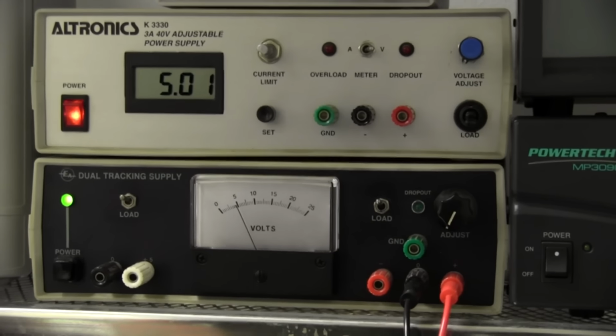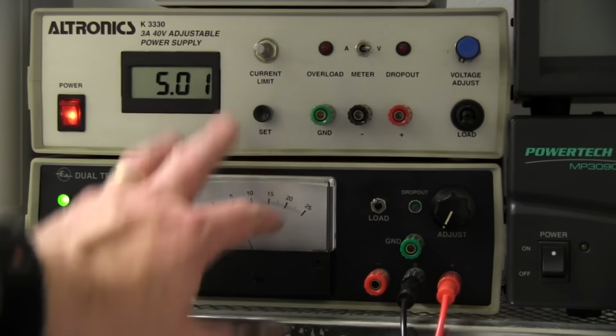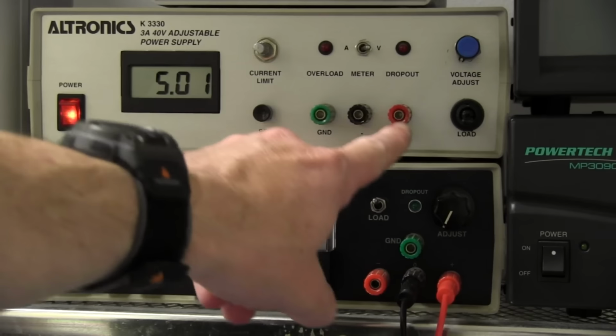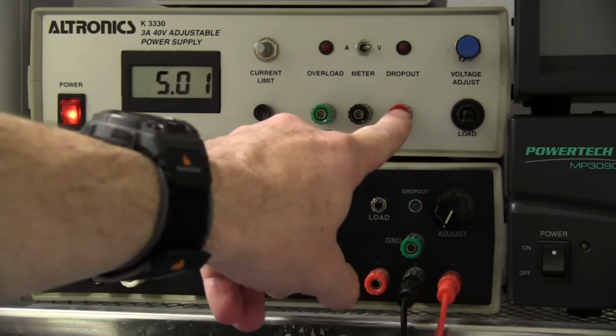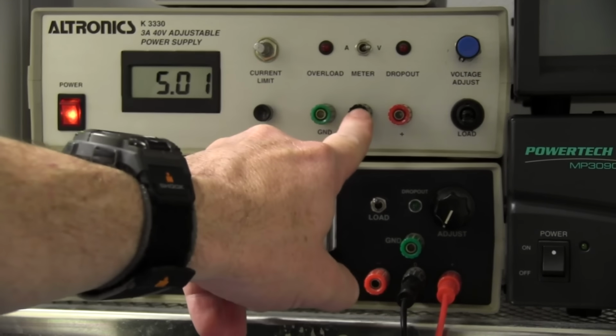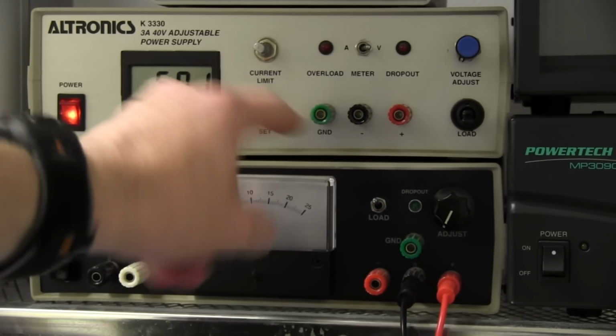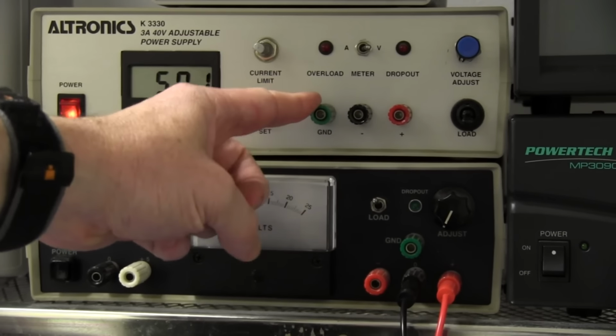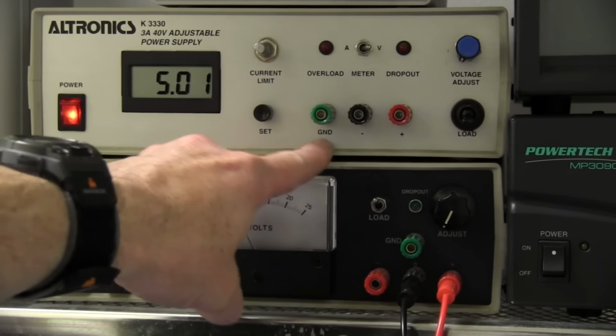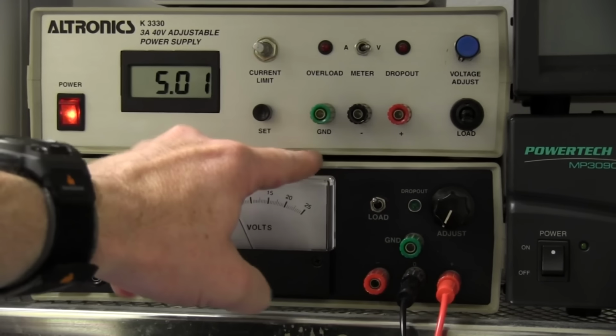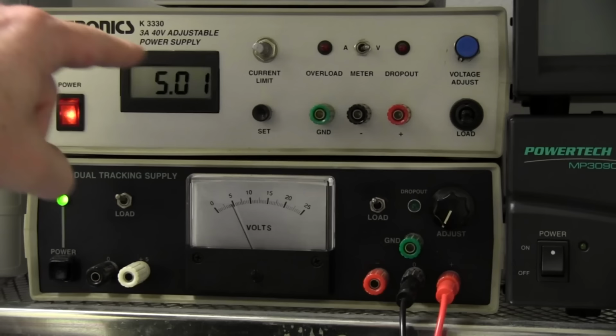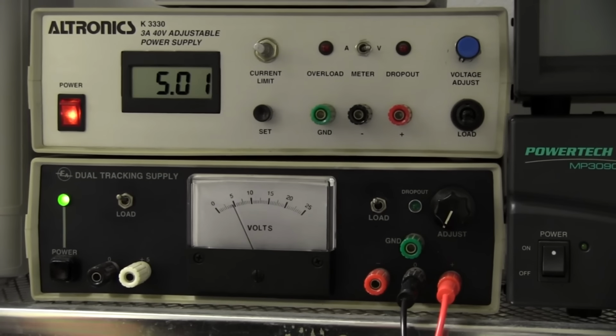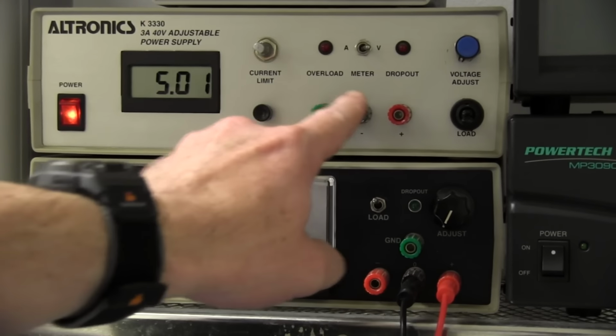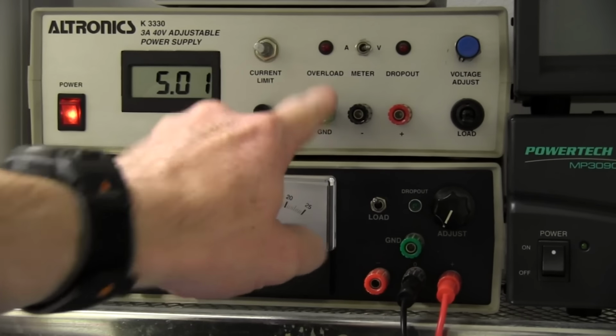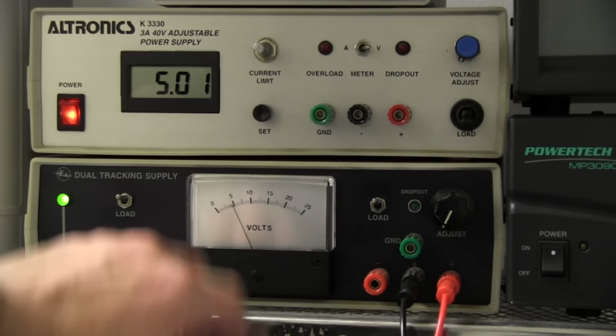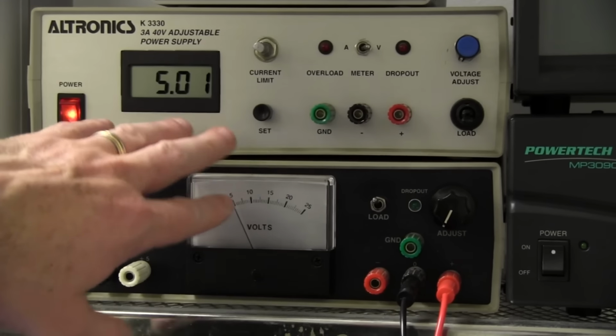Beware. Now let's have a look at some bench power supplies here. You'll note that any good bench power supply will have 3 output terminals, positive, negative, and what's usually a green one, which is a dead giveaway, which they call ground. Okay, it might be called ground. That's actually mains earth back on the mains input lead on this thing. So normally, if you don't join these together, if you haven't joined them together at all, these power supplies are floating. They're completely safe.